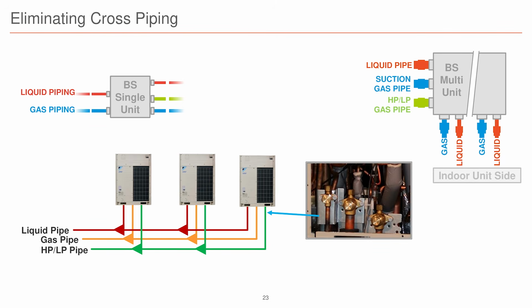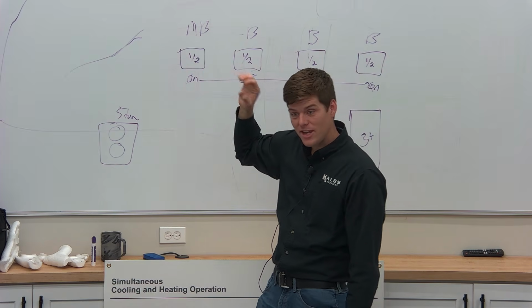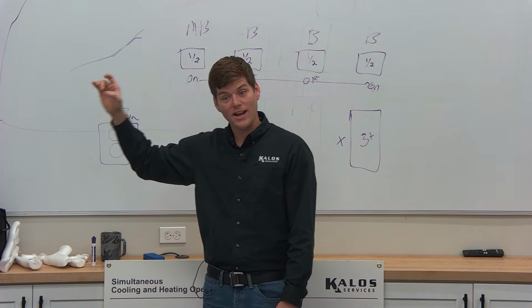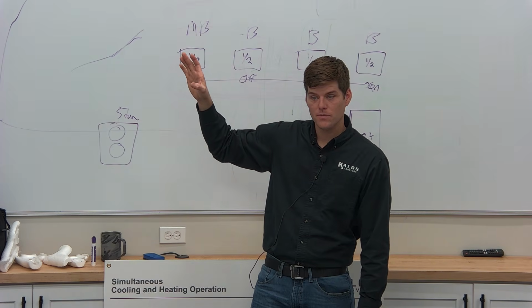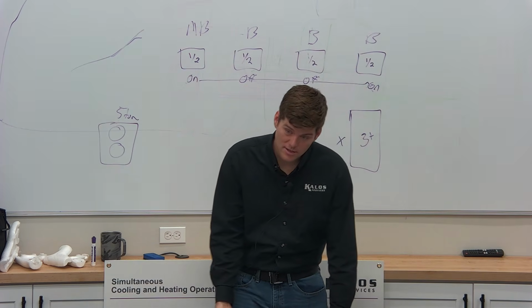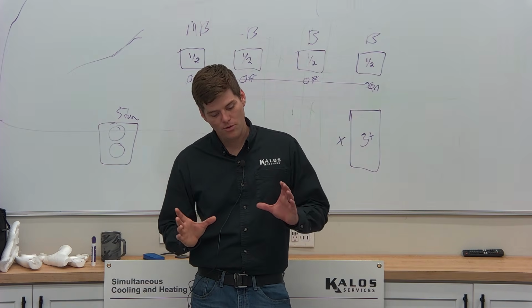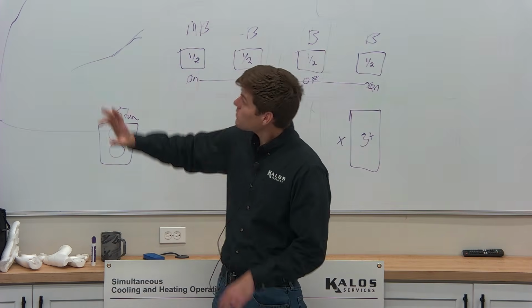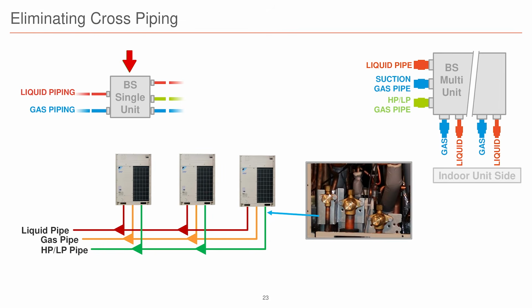This is your BS boxes, right? Single port, multi-port. The reason I threw this in here, look at all these lines. On the outdoor unit, do you see anything in there that's got giant signs or blinking lights that tell you what's what? No, it doesn't. As an installer, it would be very easy to confuse what lines go where, and it happens a lot more than you think. Know your product. Look in the installation manual. Look for a label, because you'll notice on the single port BS box, on the 3 lines that come to the box, 3 lines from the outdoor units to the BS box, they've got lines mixed up. They did that just to hurt your feelings and make problems, right?